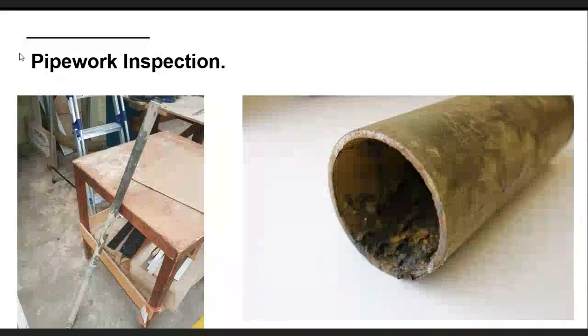Pipework inspection then. We want to internally inspect the pipes for corrosion, for health, for wall thickness, for evidence of microbial activity, all those kinds of things we're interested in. So how do we do that? Well, the most obvious way of doing it is to actually take some pipes out. Again, the standards will point you in the direction of what exactly should be inspected. We'd like a little bit of everything really. We'd like different sizes of pipe in different locations to give us a good picture of the overall pipework in the system. It's not a good idea to take all the pipe from one location because it's not really representative of the system as a whole.